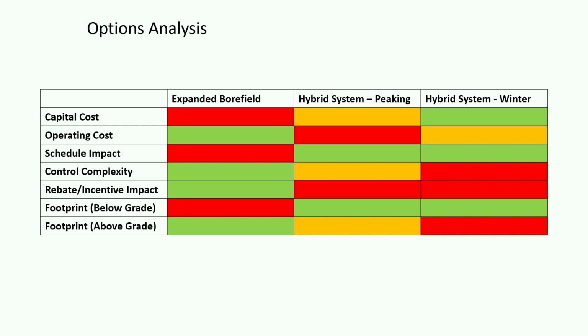And finally, all of this stuff takes up space. As we talked about, roof space is very valuable, to put a dry cooler on the roof, to put a chiller on the roof. They're noisy. We've had some instances where we want to put this up and run it for a long time, but they're saying, hey, we have a pool on our roof. People using the pool don't want to listen to our dry cooler running. So it's another factor you have to keep in mind as you're making this decision between any of these three options. And as we said before, of course, the footprint in the ground is enormously important, particularly in these tight, high-rise buildings and the places you would be installing them.